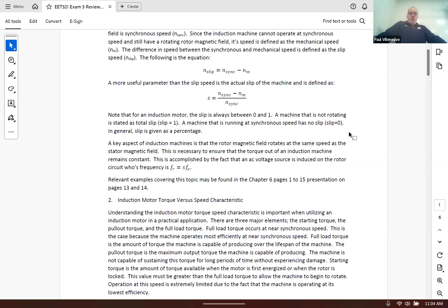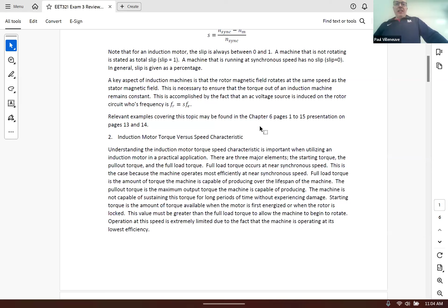So on a three-phase induction machine, on the rotor circuit, you actually have a variable three-phase variable frequency device. And as I mentioned in this class, it wasn't that long ago, they had things called rotary converters that if you could access the rotor circuit, you could have a three-phase set of AC windings at whatever frequency within reason that you wanted. Okay, so pretty important to look at that. And then you can see some examples. If you go back into the examples, you can take a look at some examples there.